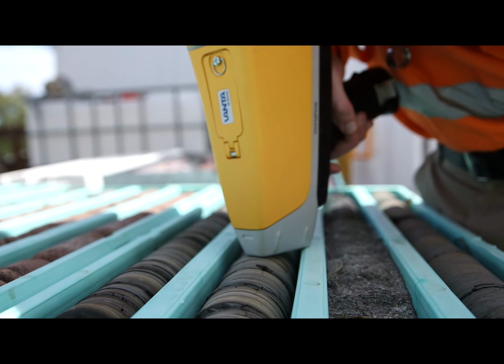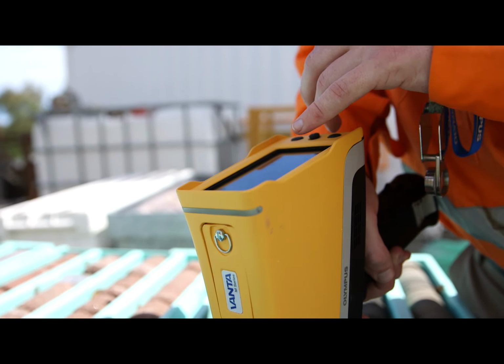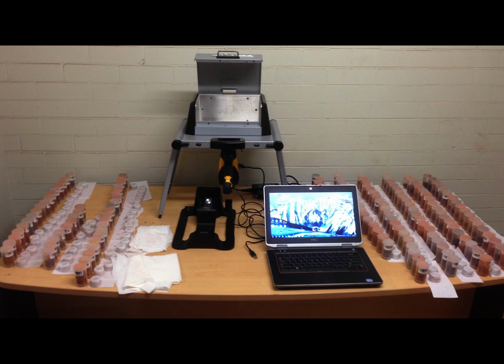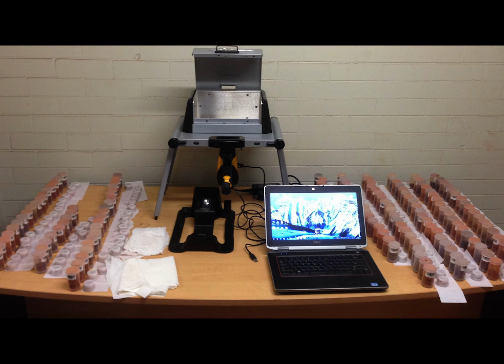So we try and calibrate that in the factory in Boston. We use a range of certified reference materials covering multiple matrices, and we teach the analyzer to read all those samples correctly to create a generic calibration that should be suitable for most geological environments. But the reality is we can't replicate every possible geological scenario. So what does that mean for a user? It means we may not get the right answer for every element every time.